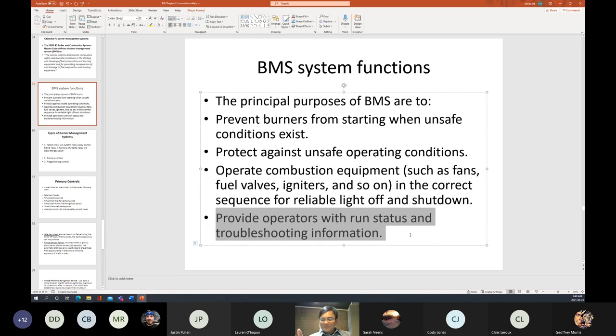So when the boiler trips, they will tell you why it tripped. Hour is not really good, hour is only a number. So lots of times it says Lockout 28. If you go to Lockout 28 on the menu, I think it could be just a flame fail, because usually anything happens, the flame fail is the first one to shut everything off because it's electronic, faster than anything. So those are the troubleshooting information they give you.